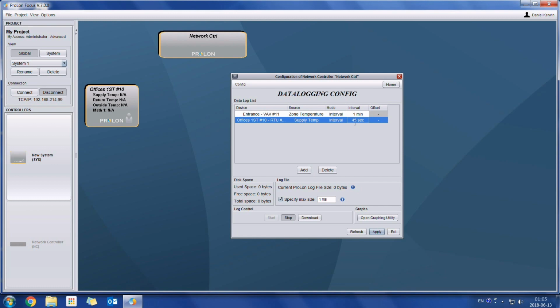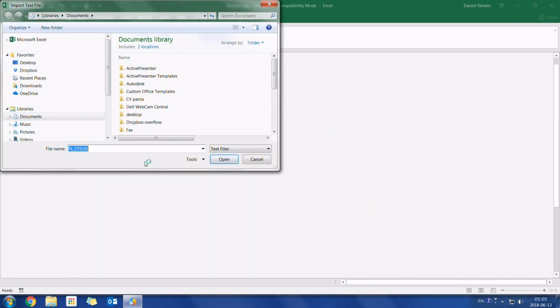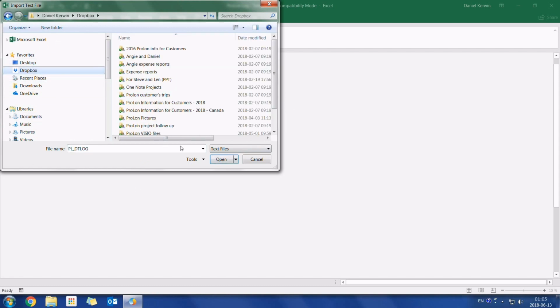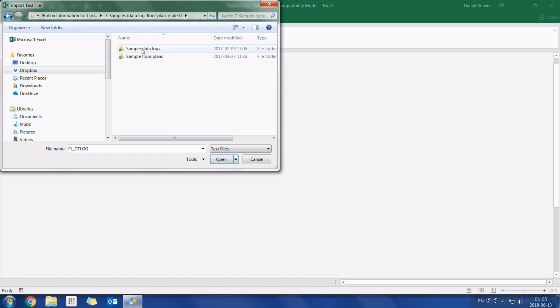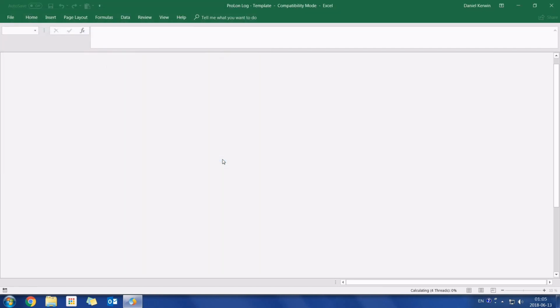With all that space, you will have more than enough room to have a data log which could go on for months or even years, depending on the amount of logs and the intervals which we choose to put. If we want to take a look at the trends, I can simply click Open Graphing Utility right here. When I click there, Excel opens automatically, and it's going to prompt you to import your data log file. I have a sample one right here. So here I have a 36-hour log. I will import it.